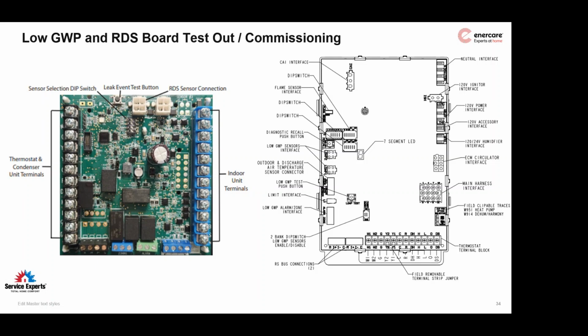To confirm the low GWP sensors and safety controls are functioning, you will perform 2 very simple tests, which are very, very quick. So let's assume we've got a standard system with one sensor, and it's connected, as you can see pictured, to sensor port number 1. In our example, let's assume we'll use this A2L equipped control board that would be from an SLP 99, or on the left is the legacy furnace with the external control.